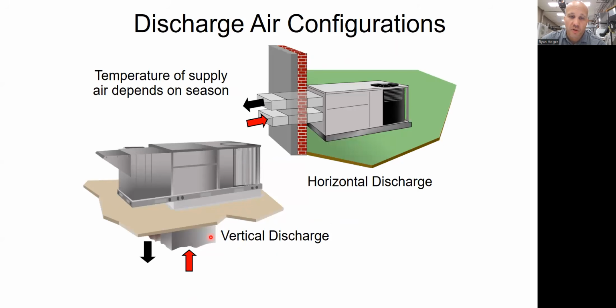All right, so as mentioned, you normally mount these on the roof, and they would have what we call a vertical discharge, which means the supply air goes down into the building, and the return air comes back up through the building. All right, so there'll be an assembly on the roof. We typically call that the curb, where those connections can be made between the piece of equipment and the interior ductwork of the building.